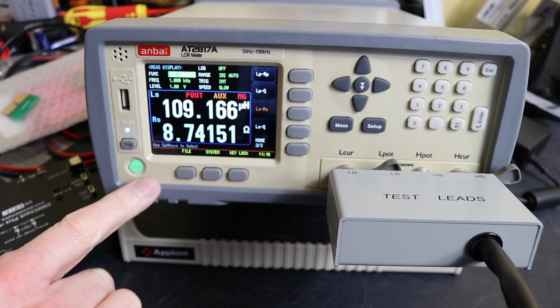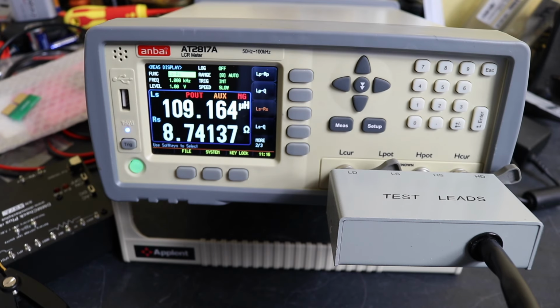But this is allegedly more accurate than the BK981 that's used by DMMCheck Plus. So I don't really know which instruments are out. At this moment in time it would kind of point to the Fnirsi being the problematic unit, because we can get the Zoyi to match a little bit, and given the whole test setup and the errors that can creep in, probably say that the test certificate from DMMCheck Plus is the correct value. But there are other methods that you can use to try and measure inductance, so I'll perhaps give some of them a go and see how they turn out.